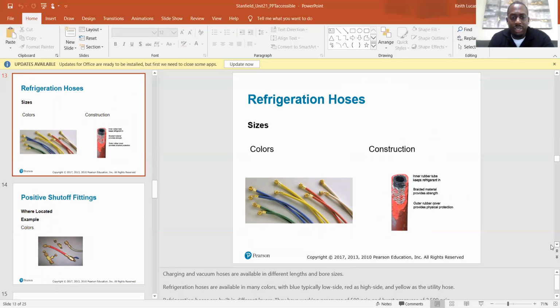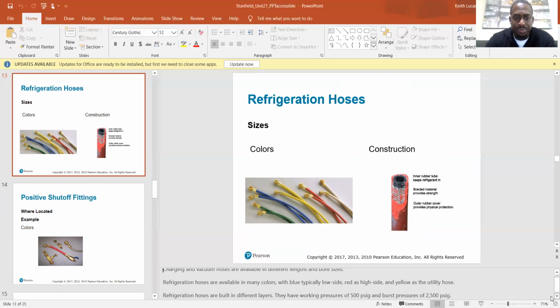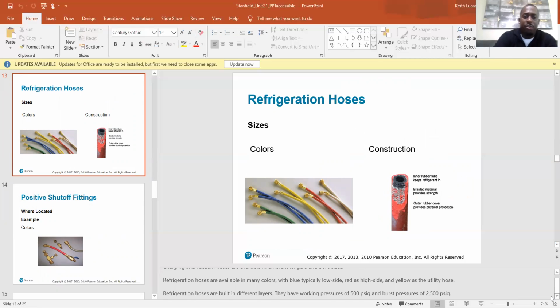Refrigeration, charging and vacuum hoses are available in different lengths and bore sizes. Refrigeration hoses are available in many colors, with blue typically low side, and red typically used on your high side. Yellow is your utility hose or your service hose. That's the one that you hook up to your nitrogen tank, your vacuum pump, your recovery machine, or your refrigerant cylinder, whatever you're doing. That's your service hose. And your blue and red hoses are always directly to your system, high side and low side.